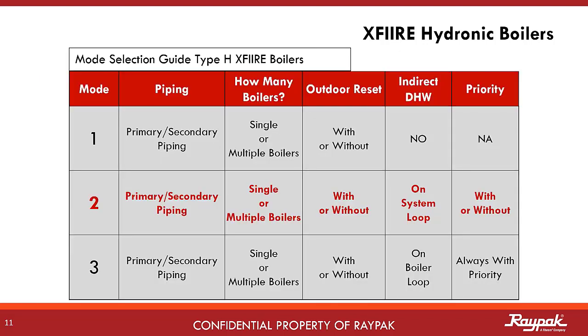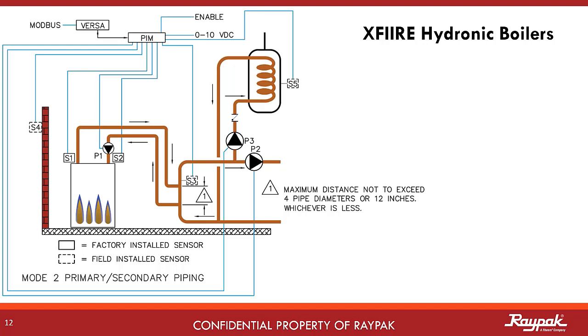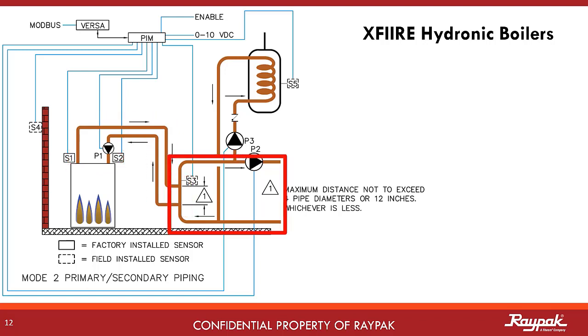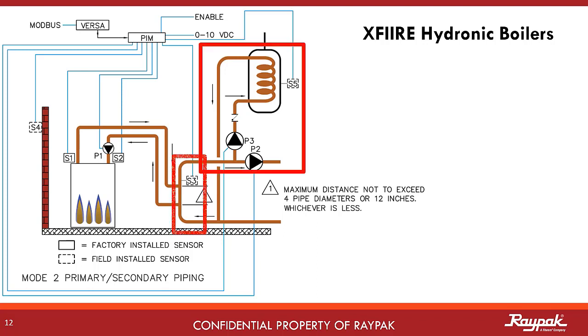Next, we will present Mode 2 for the X-Fire. Primary-secondary plumbing is required as before. The key thing that makes it a Mode 2 is the indirect domestic hot water on the system loop. In Mode 2 primary-secondary, you still have the two loops — the boiler loop and the system loop. The decoupler is still there to pressure-isolate the two loops. What makes this a Mode 2 is the addition of an indirect domestic hot water heat exchanger tank on the system loop.